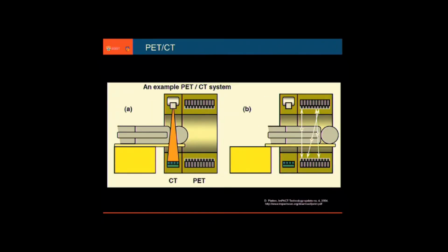In PET-CT, the CT is normally performed first, preceded by a scout view, which is used to define the axial extent of the scan for both the PET and CT scans. The CT is quick, lasting only seconds, and it's performed in spiral or helical mode with the bed moving axially during the scan. The bed then immediately moves to the PET scanning position, and the PET scan begins.